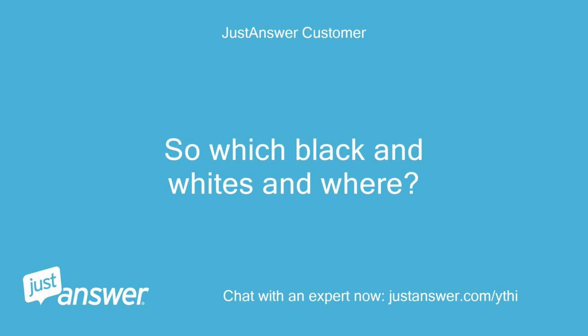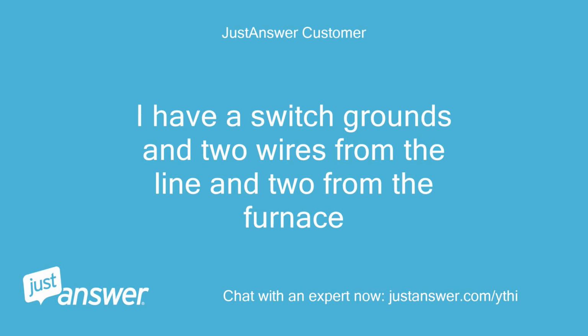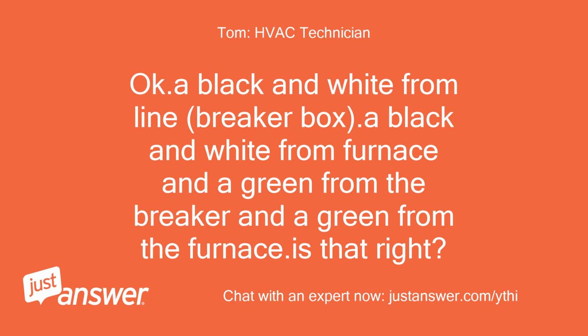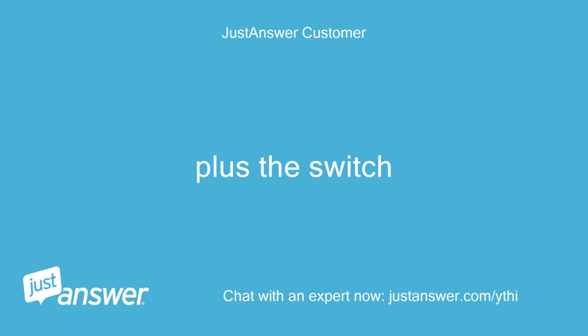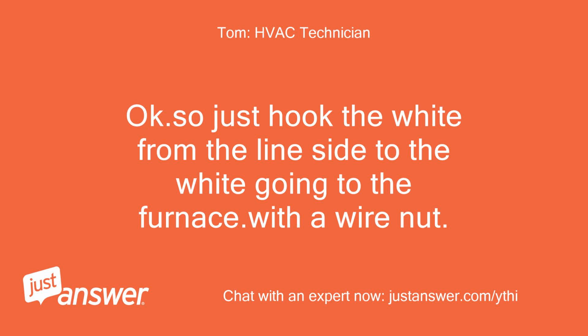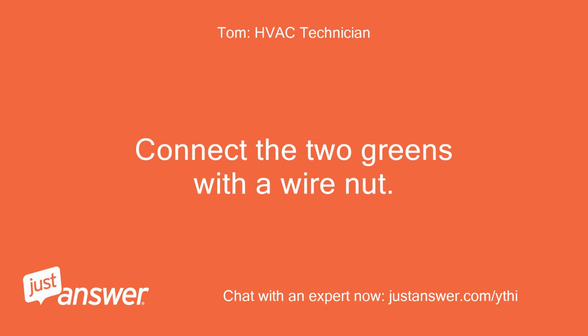So which black and whites and where? I have a switch, grounds, and 2 wires from the line and 2 from the furnace. Okay. A black and white from line, breaker box. A black and white from furnace and a green from the breaker and a green from the furnace. Is that right? Plus the switch. Okay. So just hook the white from the line side to the white going to the furnace with a wire nut. Connect the 2 greens with a wire nut.